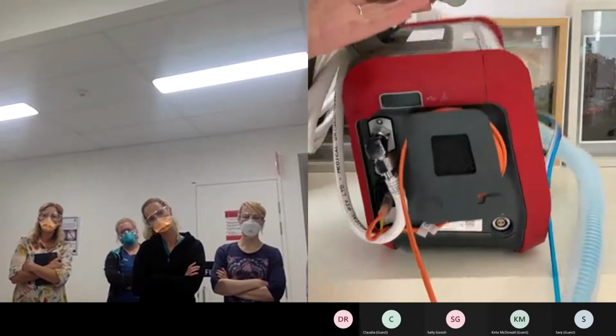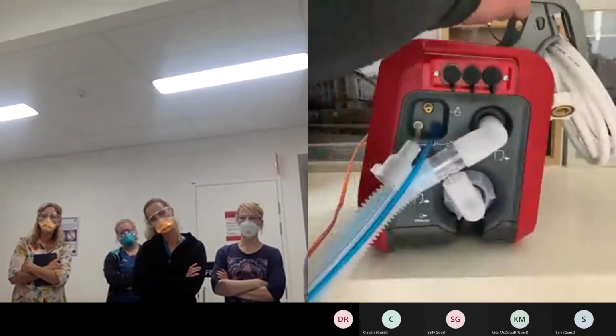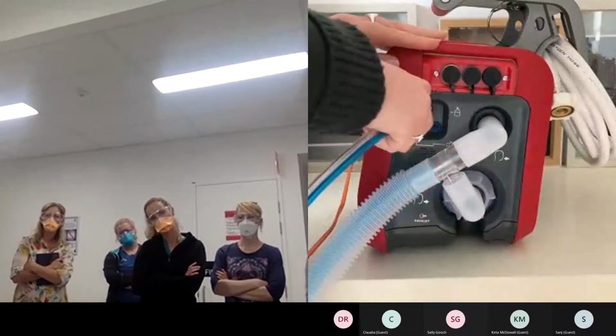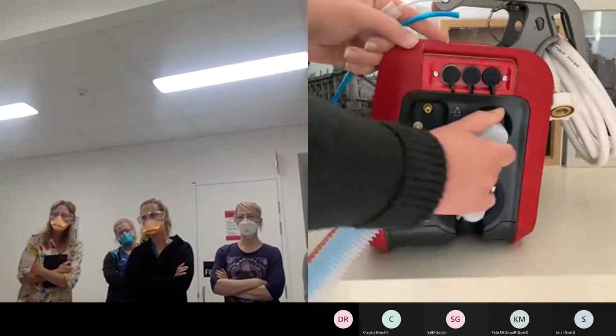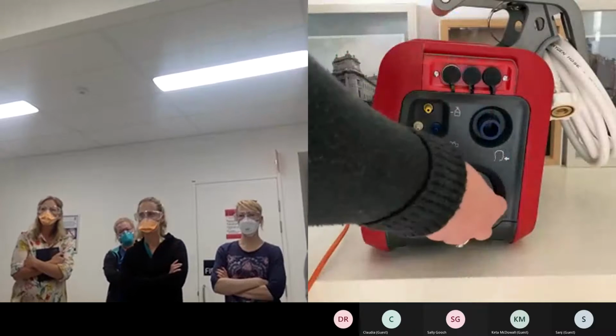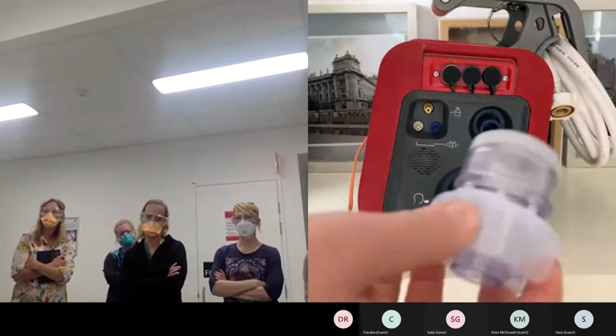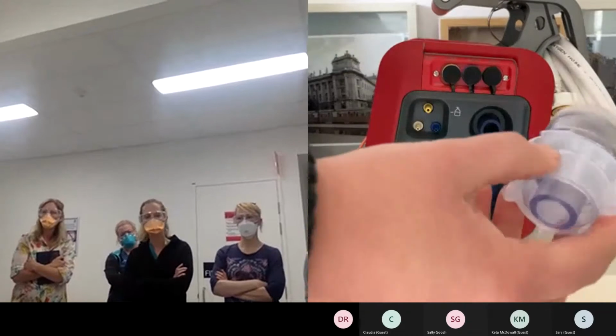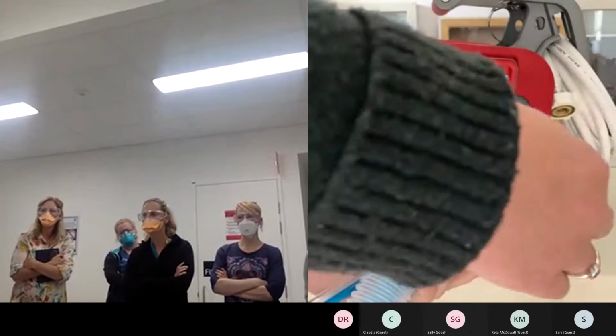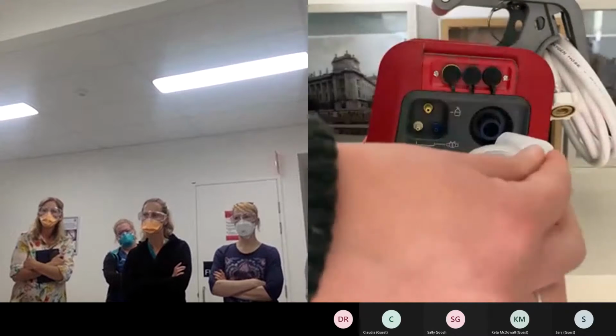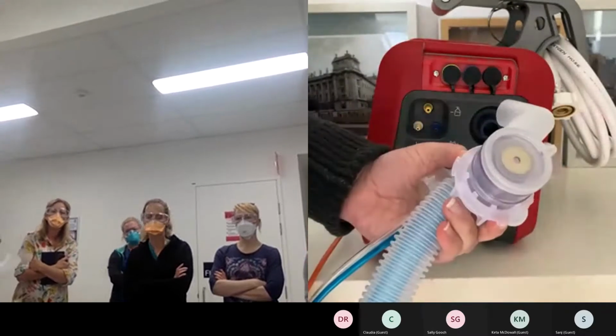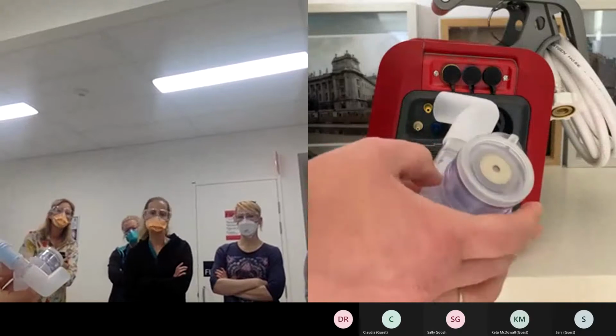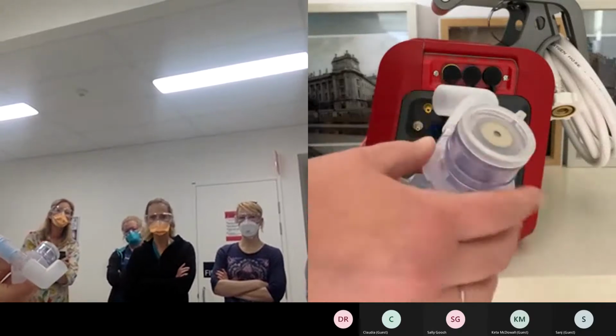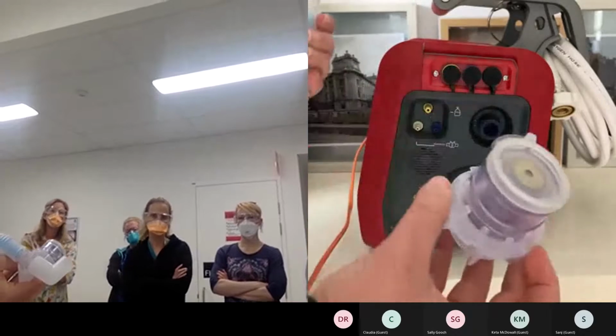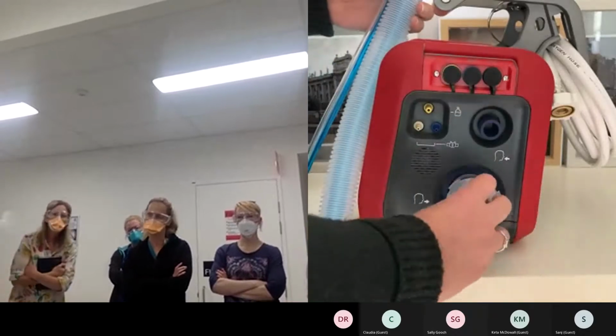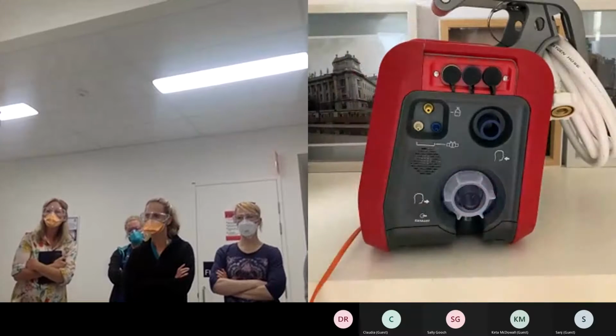Okay. And then when we come over to this side, this is the side that your circuit all gets set up in. So everything that you need in your circuit comes in the one pack. You've got this here, which is your expiratory valve. And when you look at the expiratory valve, there is this clear membrane on it. So you always want to make sure that that's sitting there tight and it's not twisted, puckered, or on the floor. When it goes into the machine, metal side faces in, and you turn and lock it into place.